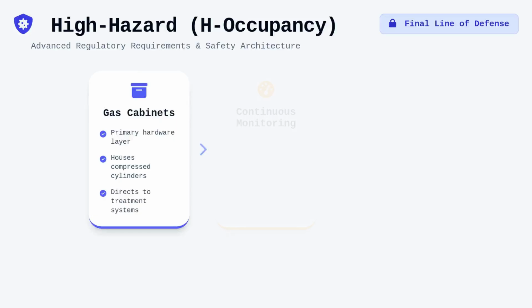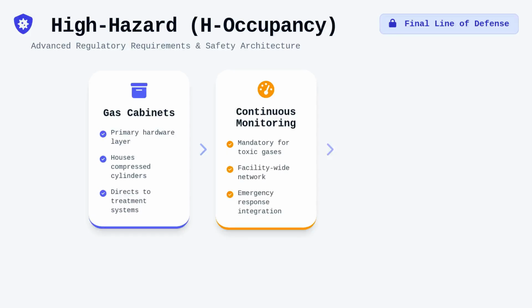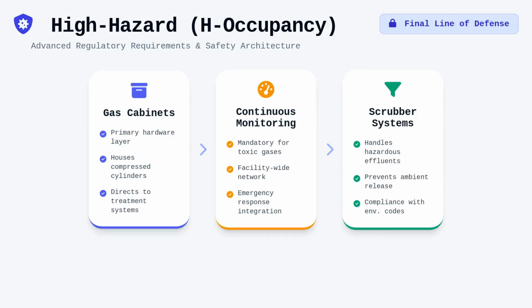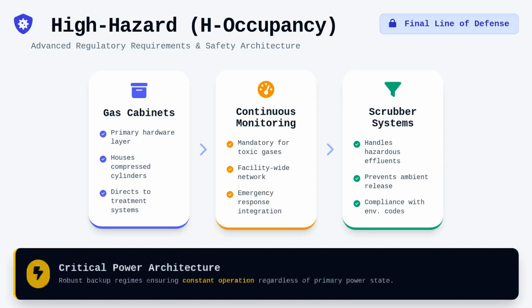In environments utilizing toxic gases, we mandate continuous monitoring systems that are integrated into a facility-wide emergency response network. Scrubbers are essential when the exhaust from these systems contains hazardous effluents that exceed ambient release limits allowed by environmental and fire safety codes. The synergy between these components, gas cabinets, continuous toxic gas monitoring, and scrubber systems, creates a redundant safety architecture. This system must be capable of constant operation regardless of the primary power state, necessitating robust backup power regimes for all safety-critical mechanical and sensing interfaces.